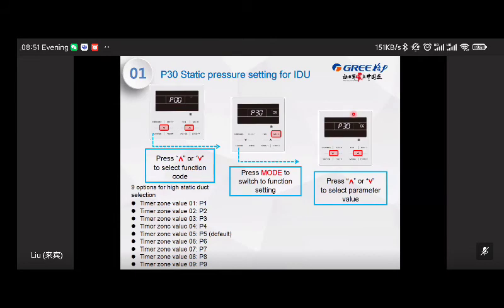Next one, P30. That's the static pressure setting for indoor units, especially for the duct type. When you install them and connect them with ducts to supply air to different rooms or areas, in order to overcome the resistance of the duct, you have to change the ESP, right? So in this code P30, you can set the ESP stage by different values. The middle one, 05, is the default. For a longer duct length, you can just increase this value. However, sometimes the ESP for that duct is too high and causes some noise.